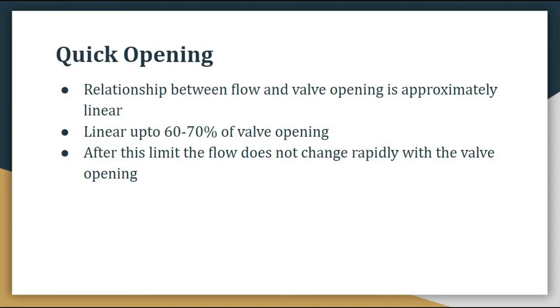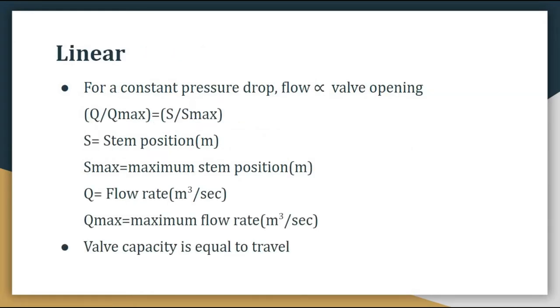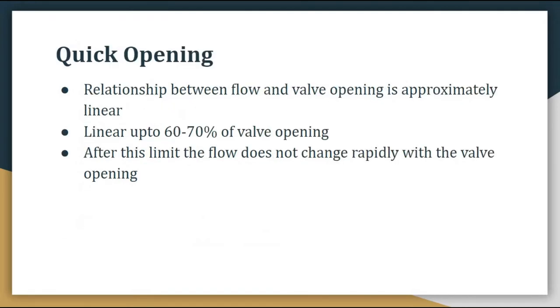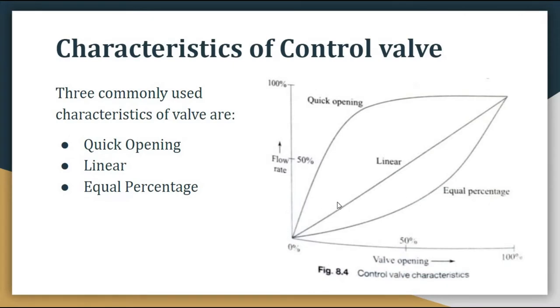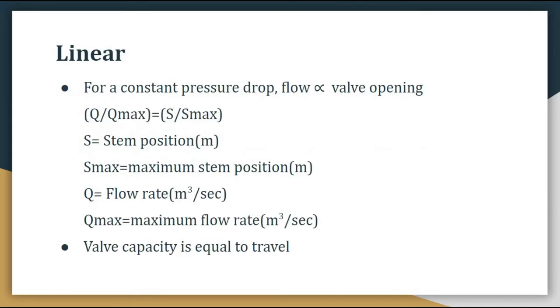The next characteristic is linear characteristic. In linear, for a constant pressure drop, flow is directly proportional to valve opening. As you can see from the graph, whatever percentage valve opening occurs, the same percentage of flow rate occurs. There is a direct relationship between flow and valve opening. The relation is: q by q-max equals s by s-max, where s is the stem position, s-max is the maximum stem position, q is the flow rate, and q-max is the maximum flow rate. In linear characteristic, valve capacity is equal to travel.